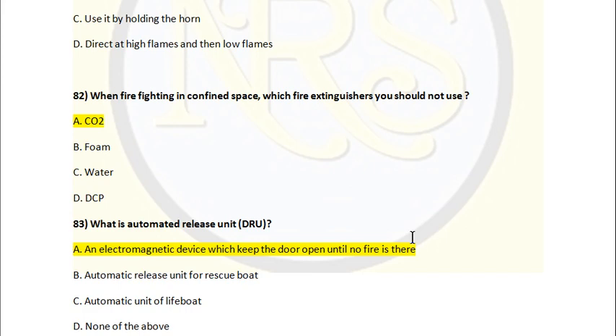If you are using a CO2 extinguisher, the confined space can be depleted of oxygen because it is heavier than air, and it will remove the oxygen from the atmosphere. This becomes an inhalation issue and can cause fatality due to lack of oxygen in the space. If the person is not carrying an SCBA set, there are chances of fatal death. So CO2 is the extinguisher we cannot use when fighting fire with a person inside a confined space in large quantity. Option A is the correct answer for question number 82.